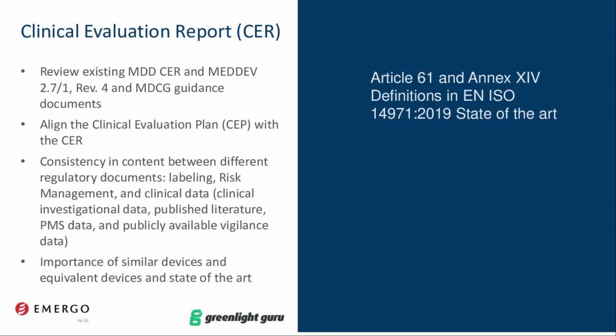And of course, Annex 14, if you're a fan of MedDev 271 revision 4, you'll appreciate that much of the structure of the guidance is included within Annex 14. As Edwin Bill said yesterday, there is no definition of state of the art in the regulation, or really formally published, that you could arrive at a definition from reviewing the MDR. But EN ISO 14971 2019 does include a definition of state of the art now. So that is a useful reference if you want to have a working definition within your procedures.